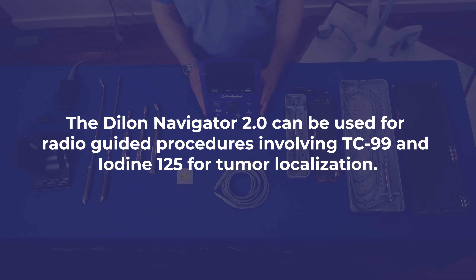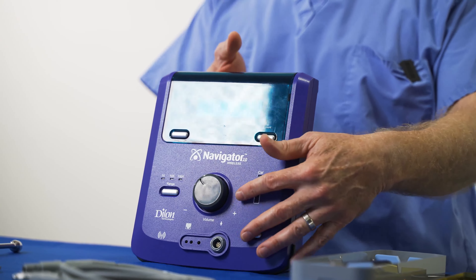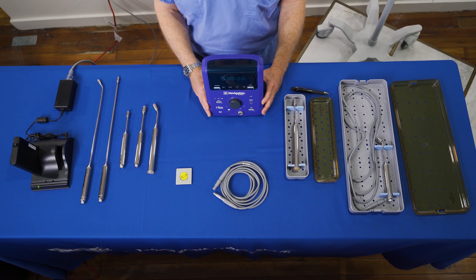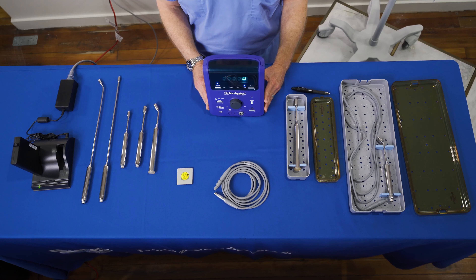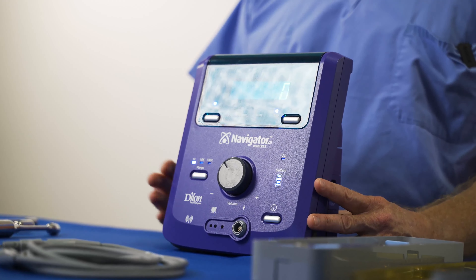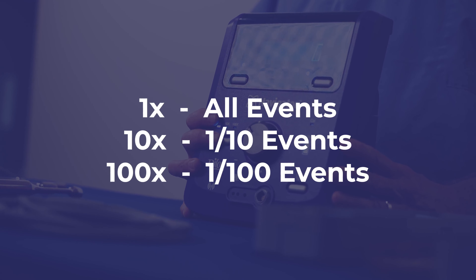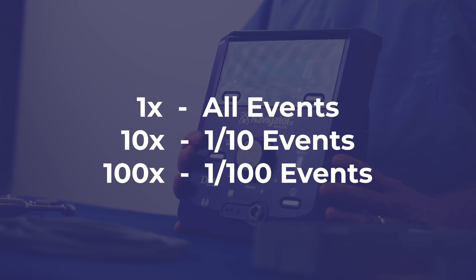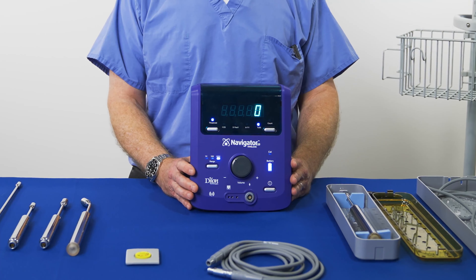The Dilon Navigator 2.0 can be used for radio-guided procedures involving technetium-99 and iodine-125 for tumor localization. On the back of the unit, you will find four source options indicating which source the system is being used to locate. Prior to the procedure, ensure that you have selected the correct source. There is an indicator light on the bottom of the display to confirm the control unit is set to the appropriate source. The system should be set to scan for use during the procedure. The range button adjusts the audible pitch to customize the sound profile for the amount of activity present. One times is for low event rates; ten times for medium event rates; one hundred times for high event rates. Pressing the range button cycles through the different ranges.